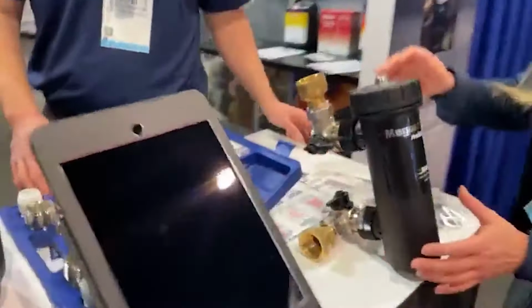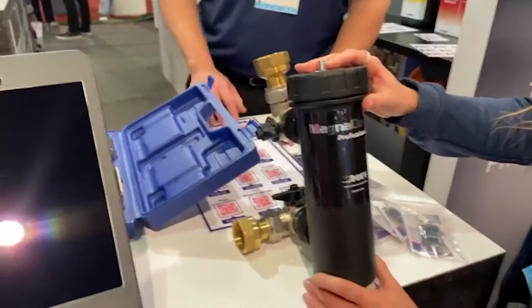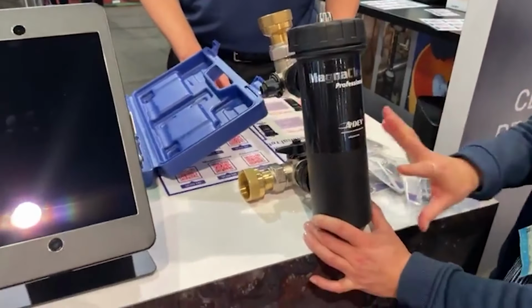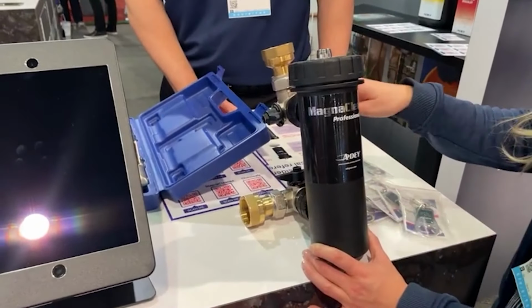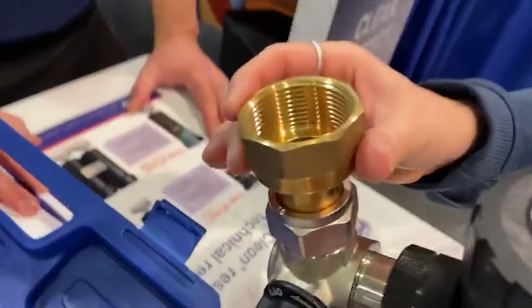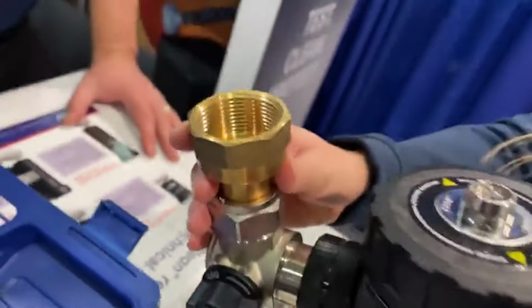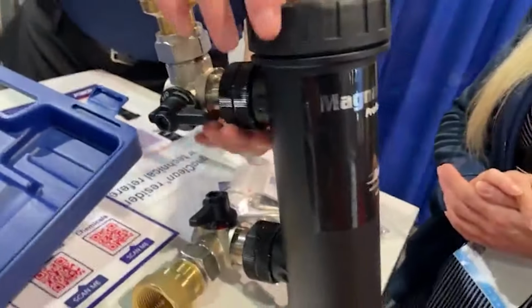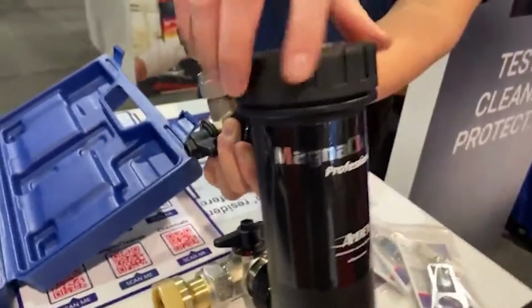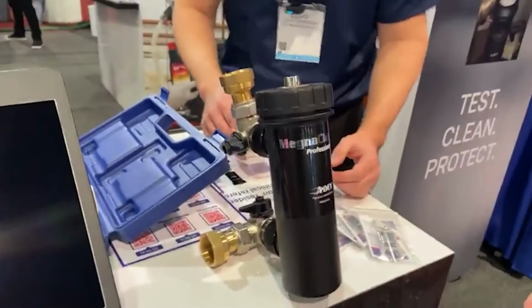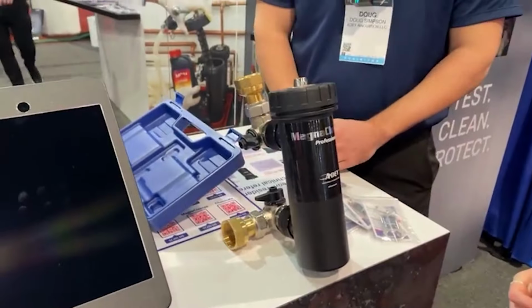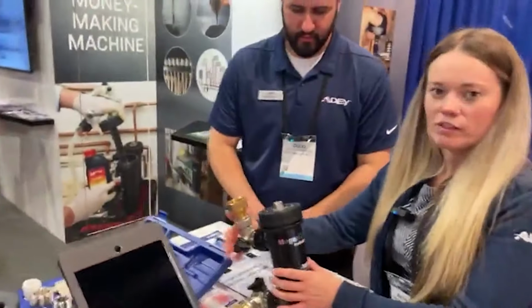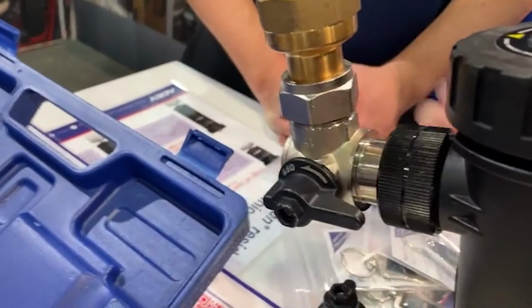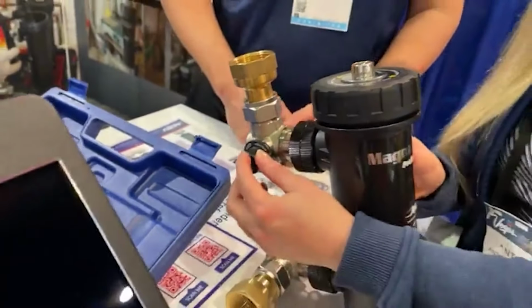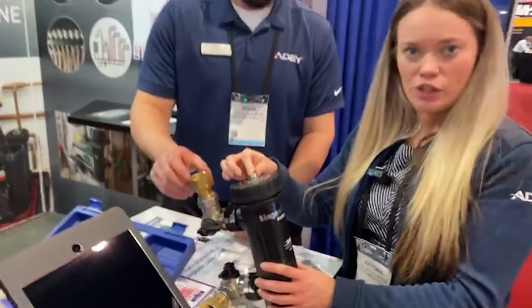This is our most popular residential filter in North America. This is our Pro 2 XP. It comes with 1-inch compression and 1.25 inch MPT adapters. It has a flow rate of 21 GPM, so it's perfect for boilers up to 300,000 BTUs. These are actually 360-degree isolation valves. To service the filter, you would simply isolate the valves, release the pressure from the top.